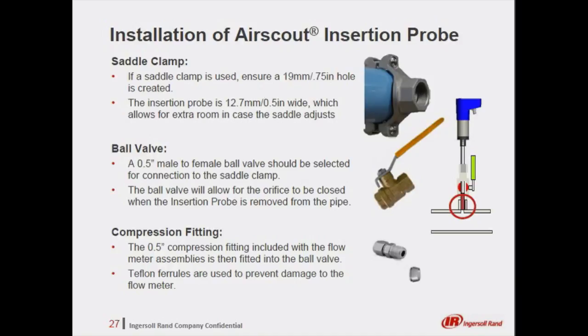A 1/2 inch compression fitting is included with the flow meter assemblies and is fitted to the ball valve. In the compression fitting, Teflon ferrules are used to prevent damage to the flow meter when being removed or reinstalled. It's critical to always use a safety chain as well with an insertion probe. All this information is available in the user's manual, which should be very carefully reviewed before installing the flow meters.